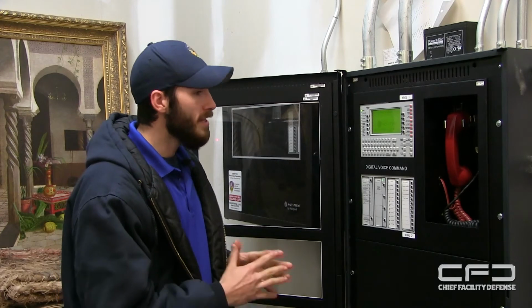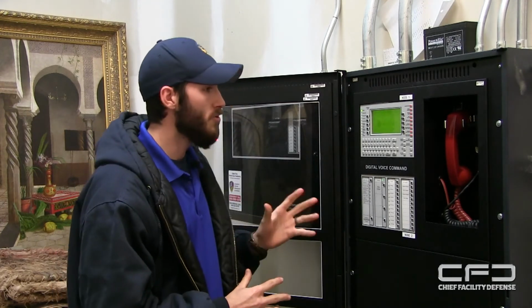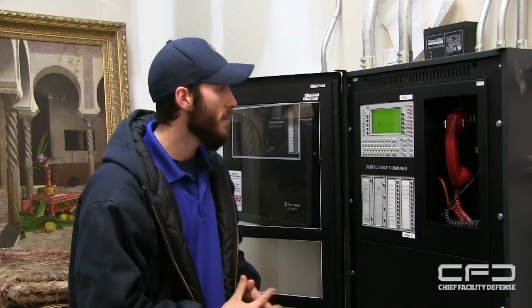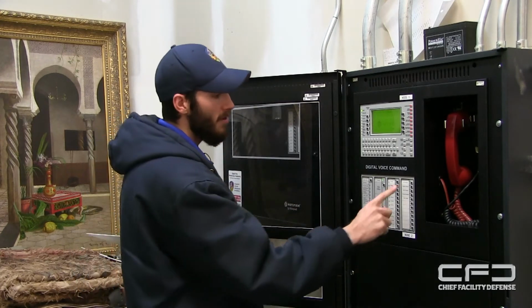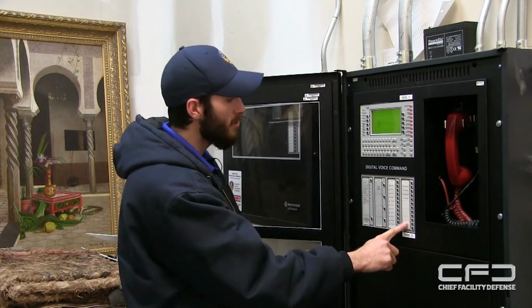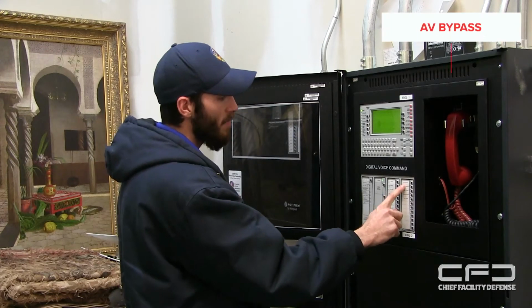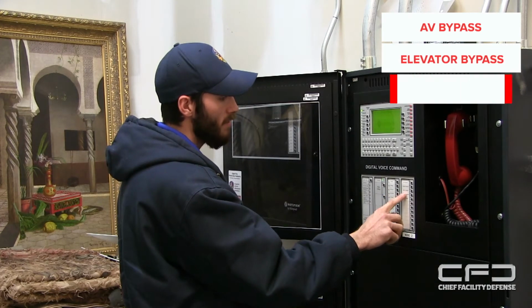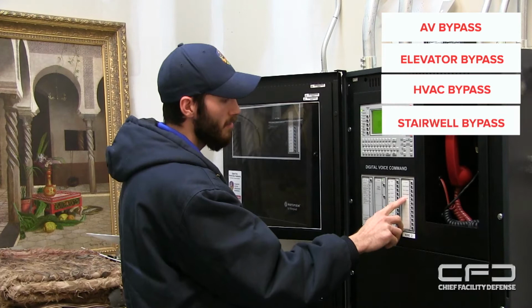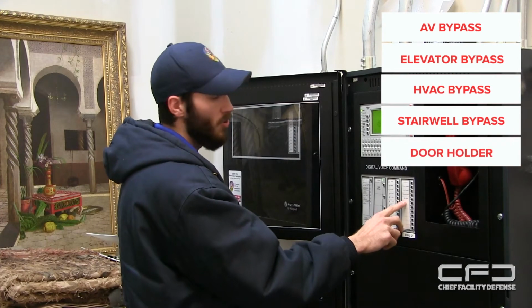If you are in need of bypassing the system, maybe you have a maintenance tech on site that needs to work on the system or needs to do construction work or anything like that, you don't want the system going off, you can locate the fire system, and down here on the bottom right hand side switches, you'll notice it says AV bypass, elevator bypass, HVAC bypass, stairwell bypass, and door holder.